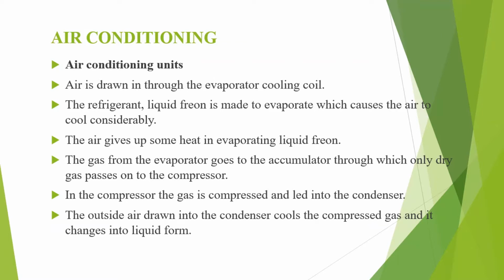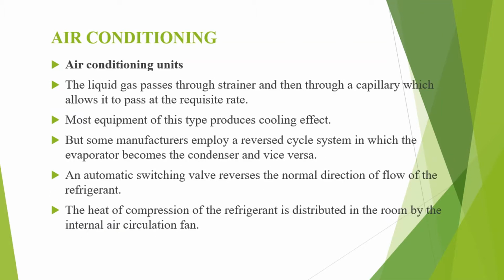In the compressor, the gas will be compressed and it will be led into the condenser. The outside air drawn into the condenser will cool the compressed gas and it will change into liquid form. The liquid gas will then pass through a strainer and then through a capillary, which allows it to pass at the requisite rate. Most equipment of this type produces a cooling effect, but some manufacturers employ a reverse cycle system in which the evaporator becomes the condenser and vice versa.